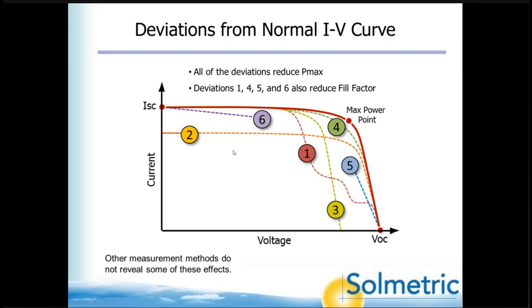So that is all preparation for this, which is leading into a discussion of the completeness of this measurement. So let's say that the solid red curve represents the expected natural good performance of a particular module that's loaded into your model in the PV analyzer. So what we expect is that the IV curve will pass through these 3 red dots, marking those cardinal points in the model. So this one does, and so that's the ideal normal curve. But in actual practice, we often see curves that deviate from the expected in 6 different ways, and sometimes in combinations of those ways. So number 1 is steps in the IV curve.